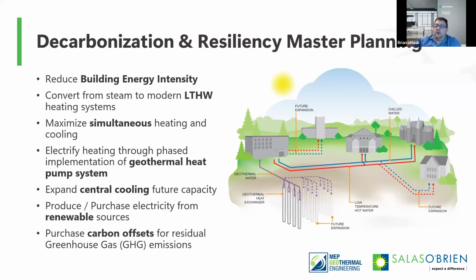At Prairie Island, we're only 150 feet deep. That's it. But we have enough water at 150 feet to supply 7,000 gallons a minute to the building. So it's really about the geology and hydrogeology of where you're working. But that's the difference between closed loop and open loop.